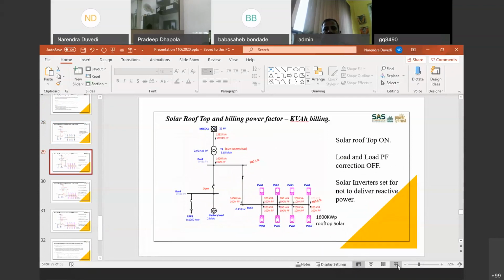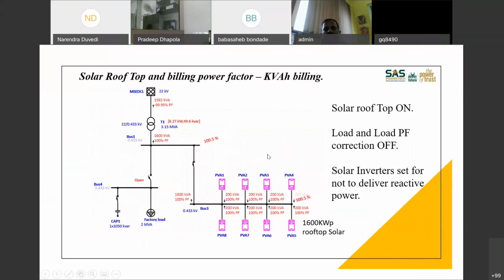This is the worst case which can happen, right? You have a solar PV installation, you have a plant running, the plant is completely not working. I mean, I just disconnected this and you are pumping energy back to the grid. Now, most solar inverters are programmed even today to generate only active power. It is not basically designed to generate reactive power. So what will happen is the entire energy generated will be pumped back to the grid.